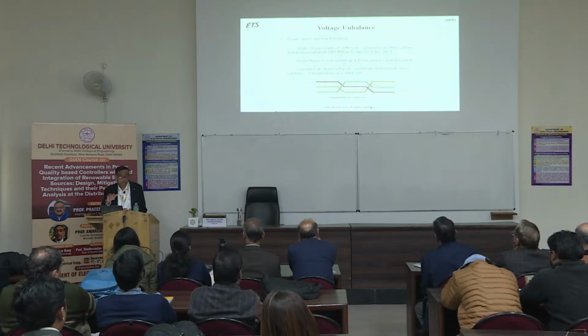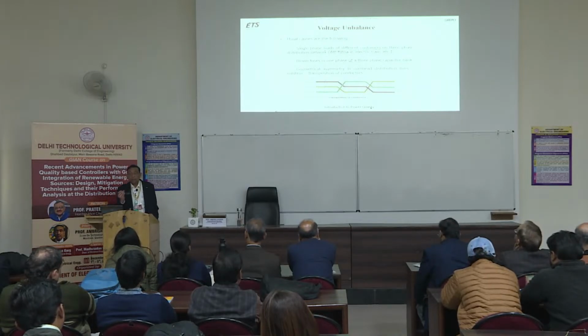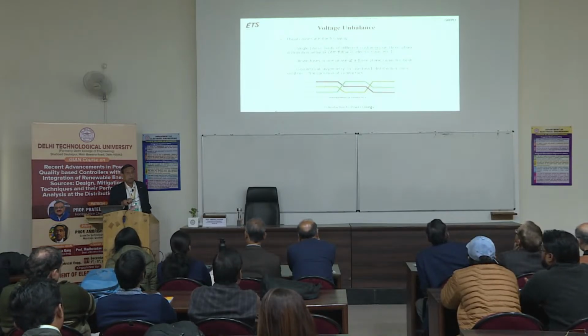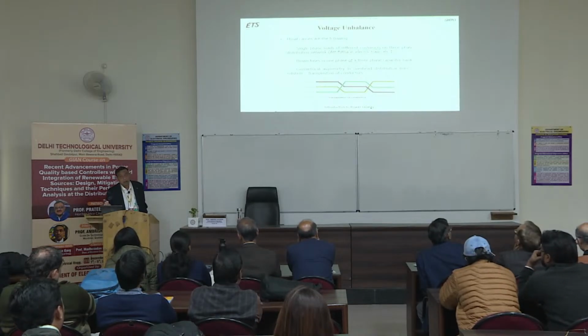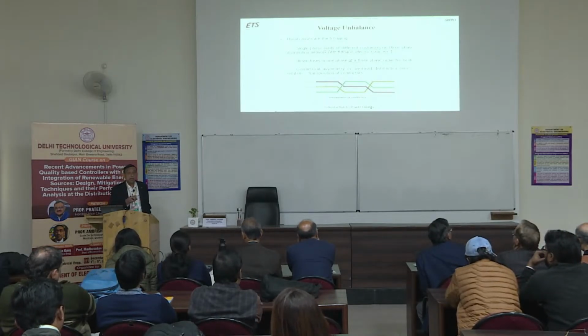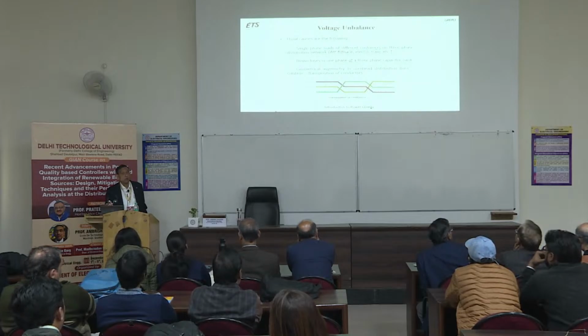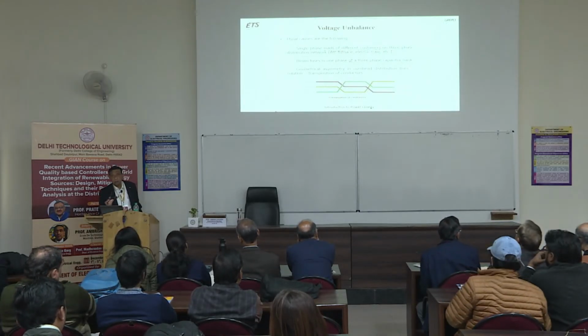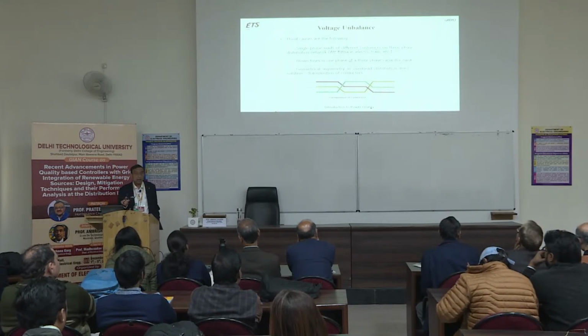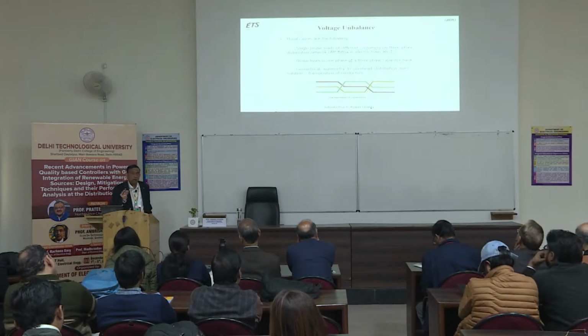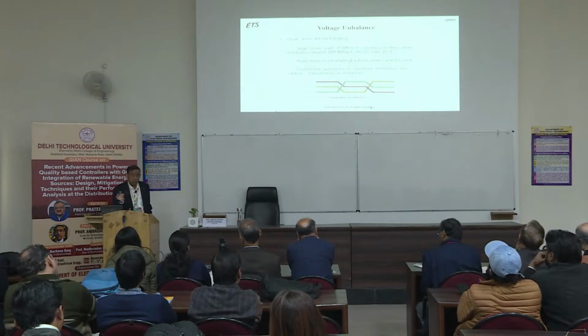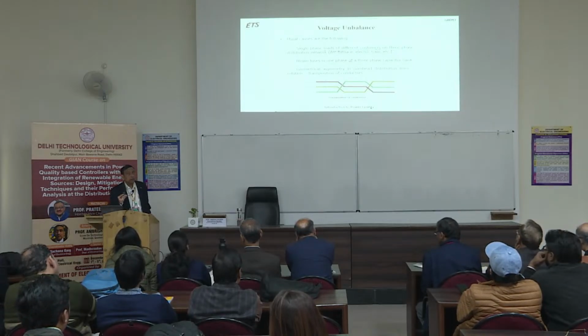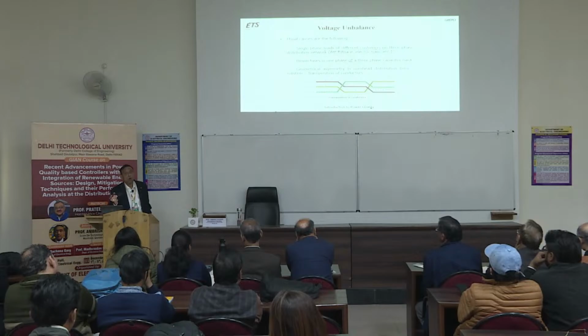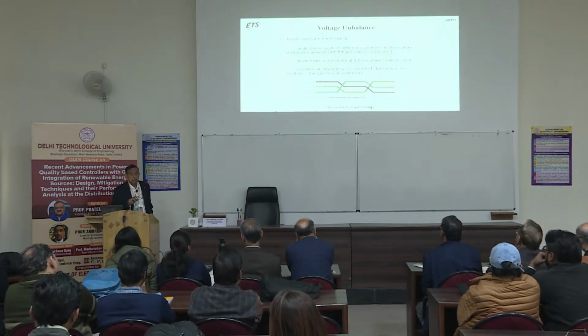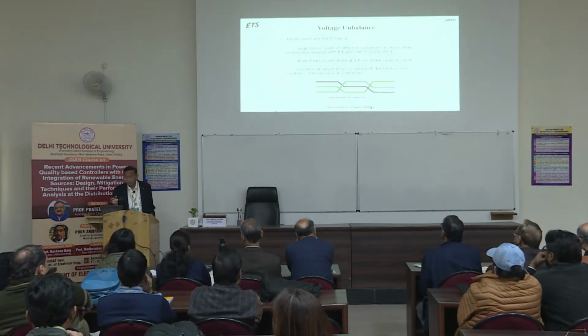So suppose you have a three-phase capacitor bank, and the fuse of one phase of the capacitor bank is burned out. So A is burned out, B and C are still providing. So the A reactive capacitive current is not provided by the capacitor bank. So it will have more voltage drop, because more reactive capacitive current is drawn for phase A from the source, while B and C are still compensated by the capacitor bank.